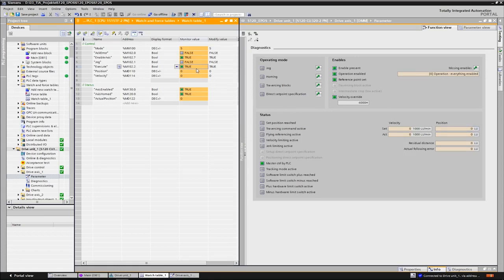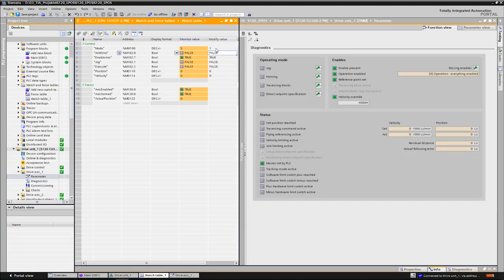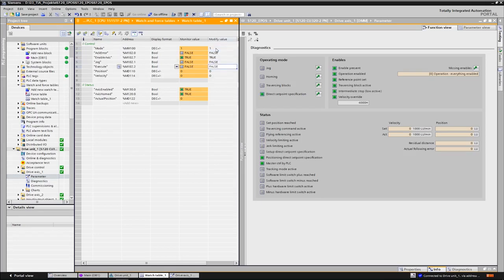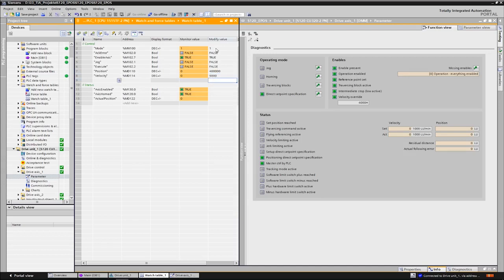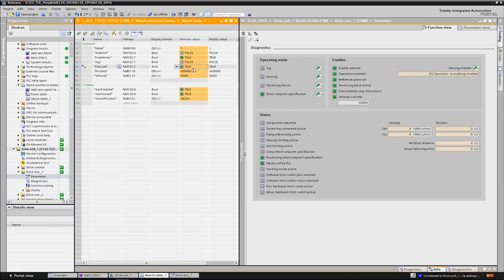From this position we want to start a relative positioning motion of 400 millimeters. We select mode 1 and specify the target position of 400,000 LU. As speed we set 5000, which equals 5 million LU per minute, and we start the task again by the execute command. We can observe the actual position and speed.